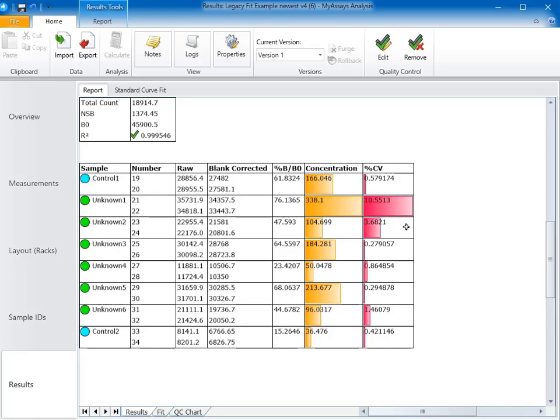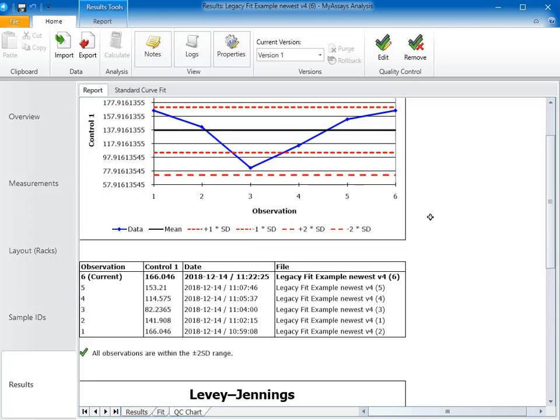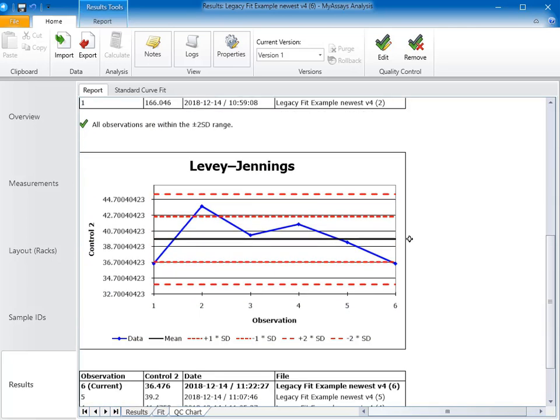The last parameter we'll check is the QC. I've used the QC option from My Assays Desktop to track and chart all observations for both controls. So on our QC chart tab, you can see that so far all of my observations have fallen between the mean and 2SD limits. And our current run is between mean and 1SD for control 1, and 1 and 2SDs for control 2.